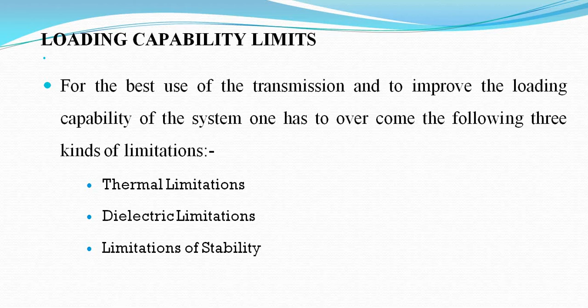Thermal limitations of overhead lines. It is a function of ambient temperature, wind conditions, conductor condition, and ground clearance. Ambient means it depends upon the sky condition, position of the sun, and other atmospheric factors. Also, the conductor temperature should be maintained within the safety limits, and that temperature depends upon the load current.